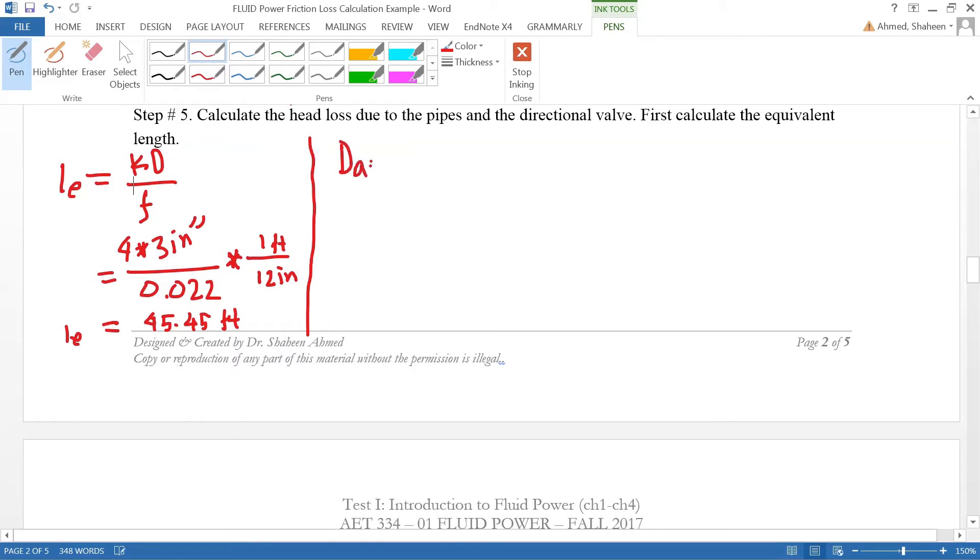to calculate the friction losses. Darcy's equation is the friction loss calculation equation: f times L over D times V squared over 2g.